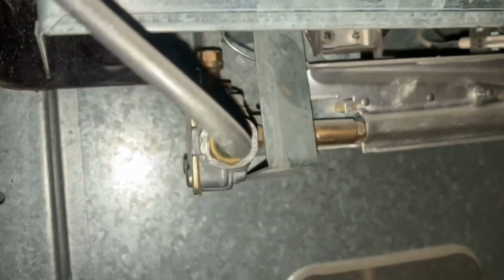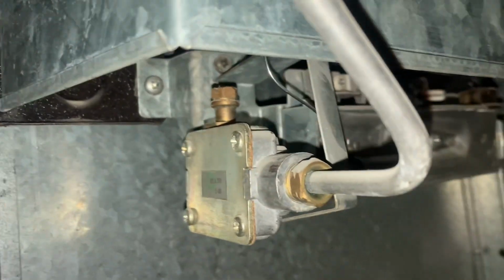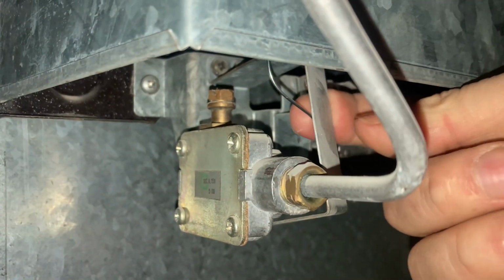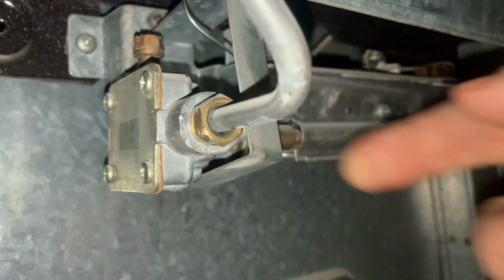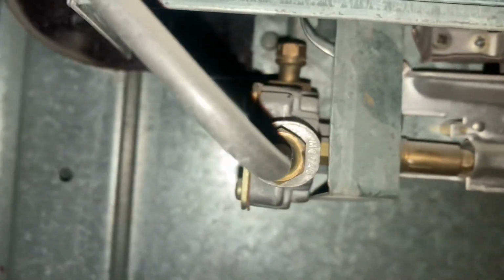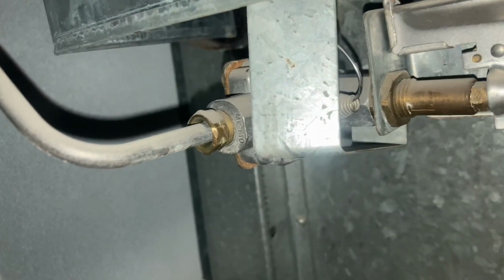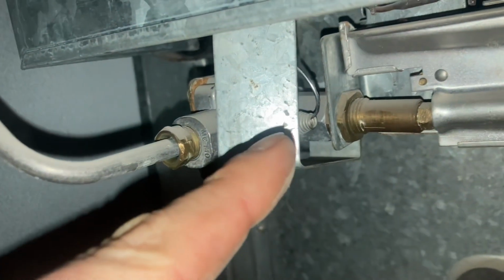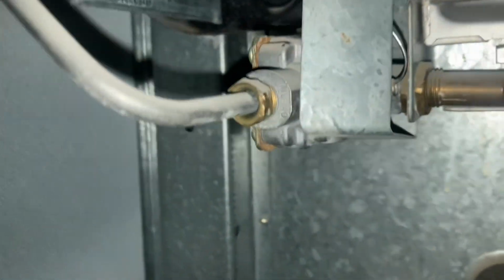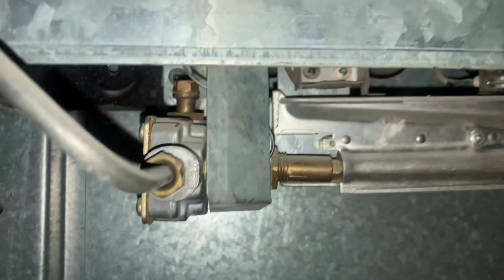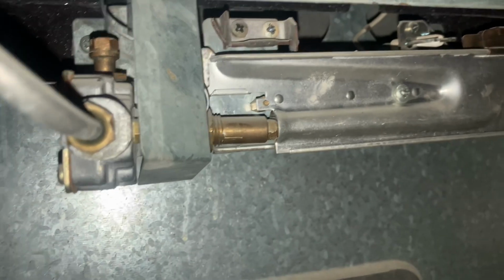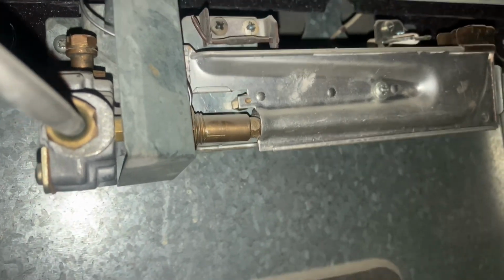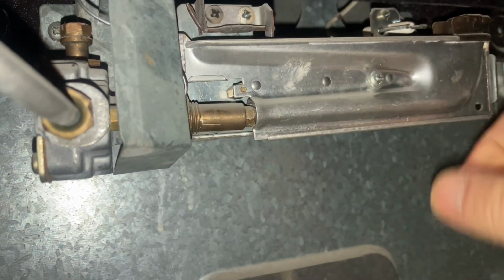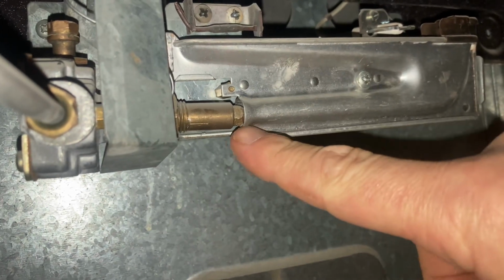Here's the burner underneath. So the flame safety device comes across, and it's actually in the side, just behind that plate. If the flame's yellow or it's not burning very good, you can take these out and just clean the injector there.